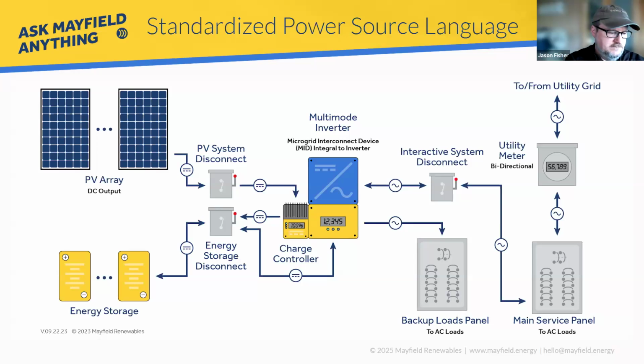There's a handful of interrelated questions, so I'll try to address them together. In this situation we're showing a DC coupled system, so call that energy storage in the bottom left corner. That's your UL 9540 energy storage system, including the batteries and probably the BMS. We have our energy storage disconnect on the output of that.